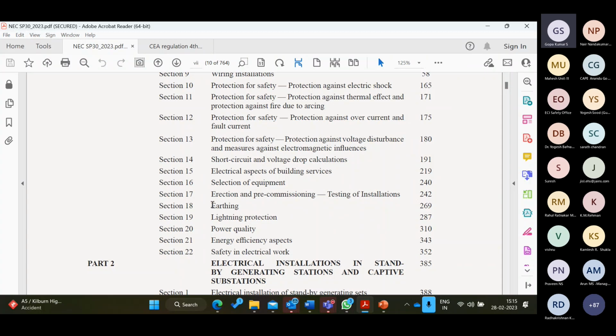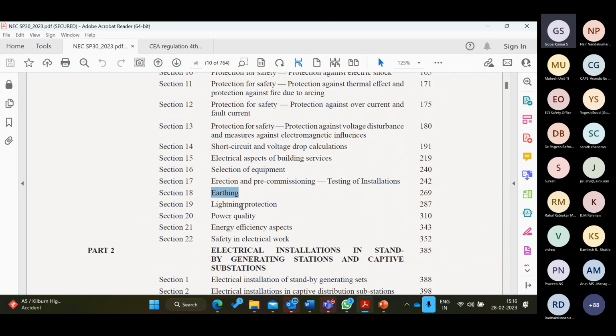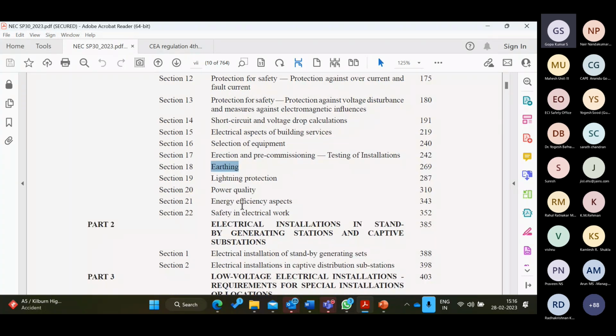One of the important sections is earthing, which, according to me, is very, very important, because if you take 100 mistakes in an electrical installation, almost 50% are related to earthing. So in this section, we have included simple pictures. It is not made as a standard, it's made as a guide, because people should understand and go through it properly. For example, section 17, erection and pre-commissioning testing of the installation.